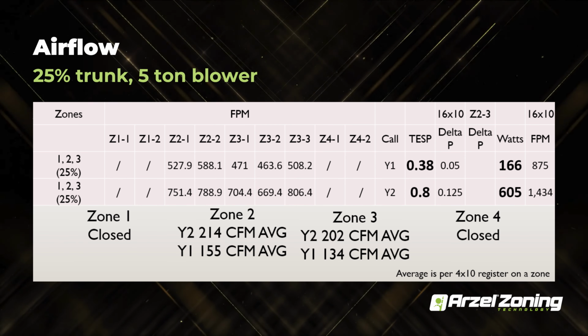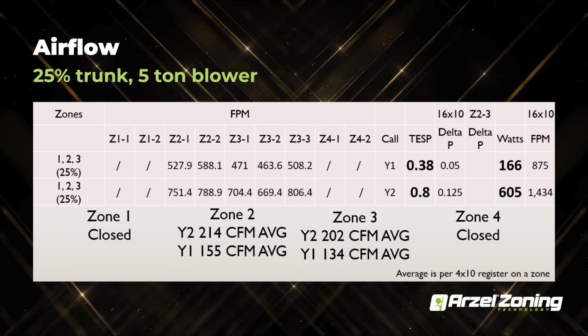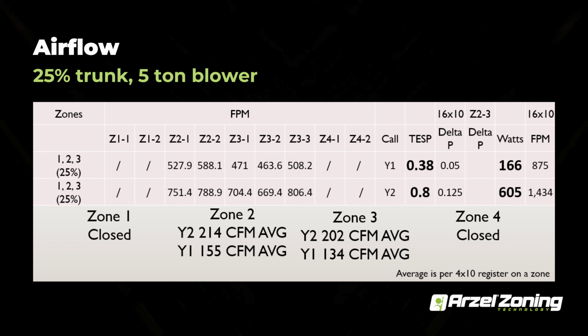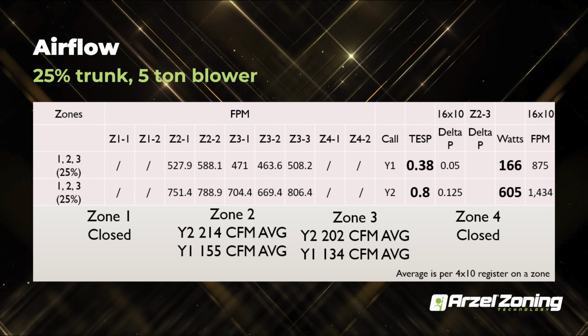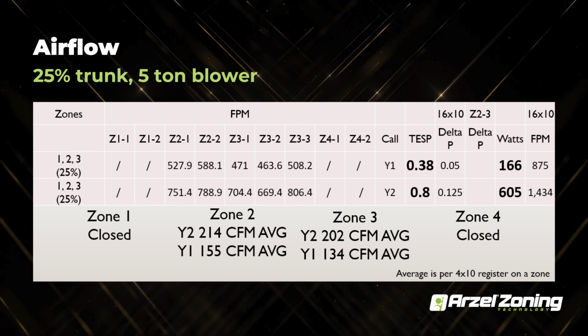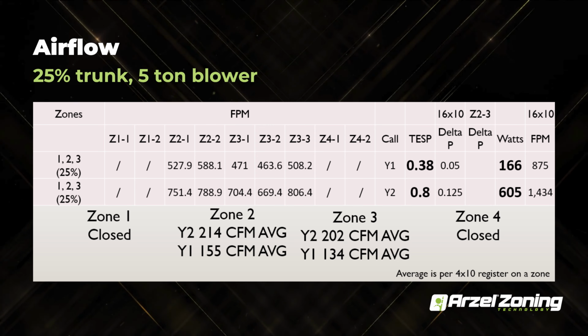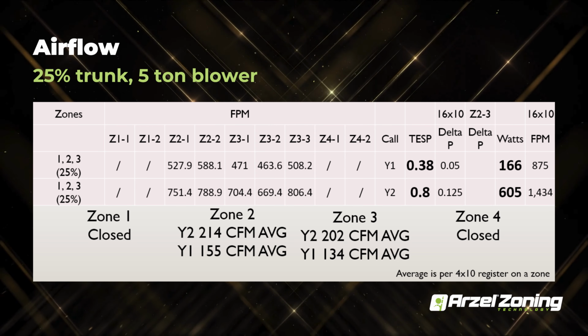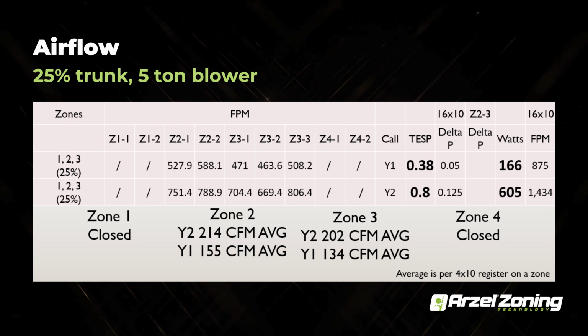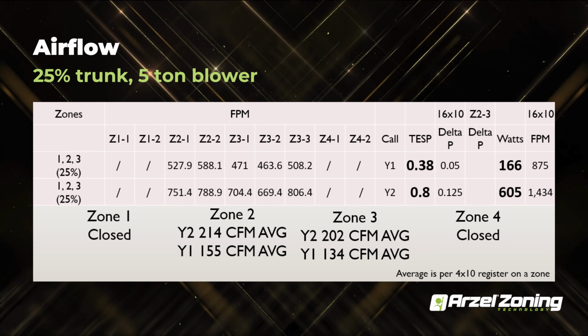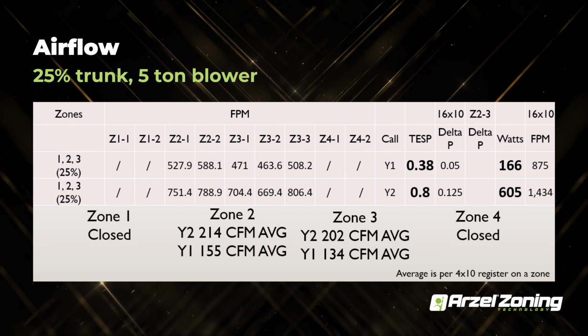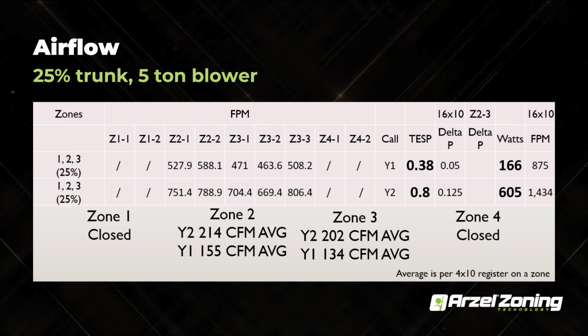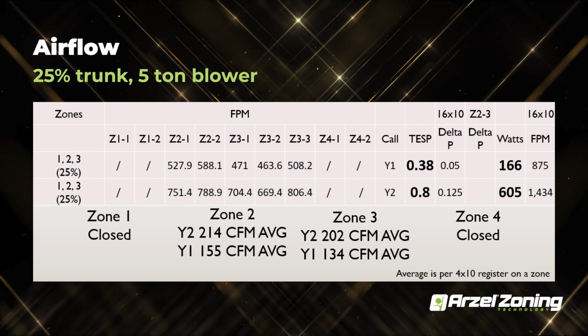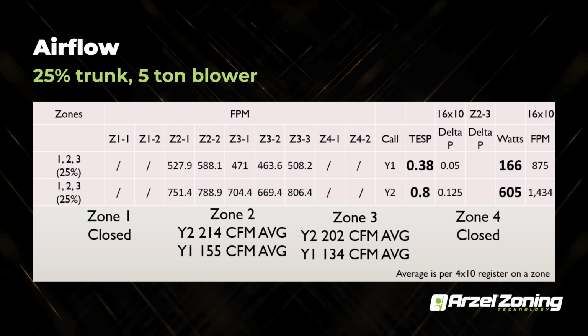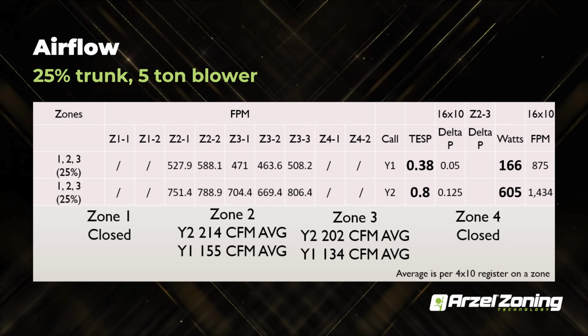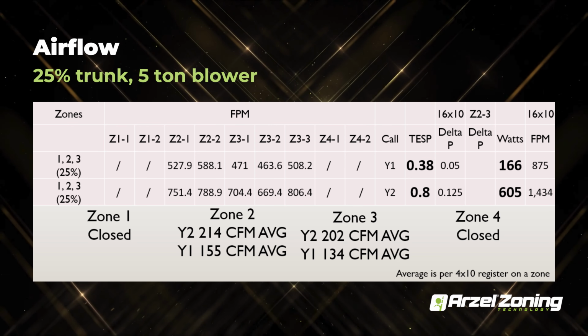So our next one that we did here is we only dropped it down to 2 zones calling, so this is 25% of our trunk. This is the smallest that we ever really want to see a zone, unless you're doing a slave function or something like that. But typically 25% on an ECM style or variable speed piece of equipment is your smallest zone. And that's going to be with a minimal bypass as well. So that's another rule of thumb for you: 25% on ECM, 35% on your PSC motors or a belt driven if you come across that still.